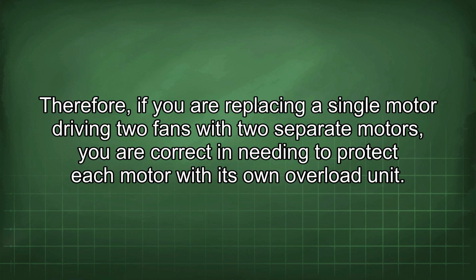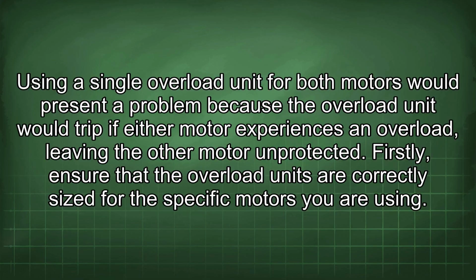Therefore, if you are replacing a single motor driving two fans with two separate motors, you are correct in needing to protect each motor with its own overload unit. Using a single overload unit for both motors would present a problem because the overload unit would trip if either motor experiences an overload, leaving the other motor unprotected.